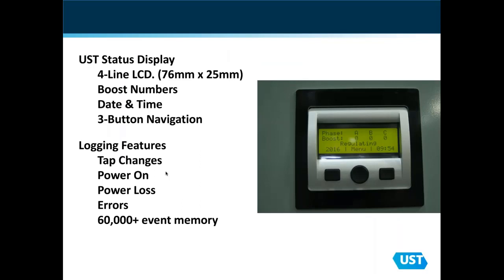The unit also comes with a 3-button status display. What we're illustrating there is you'll be able to identify which phase and which boost number we are on when we're regulating voltage. Also has date and time and 3-button navigation. It also has some logging features commonly used for troubleshooting if needed. We're going to log all the tap changes that the unit makes, and it also will display error messages as needed.